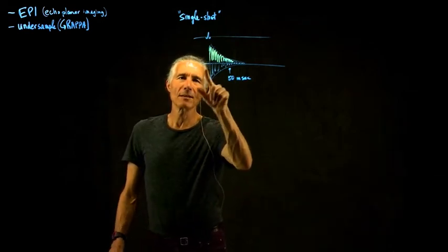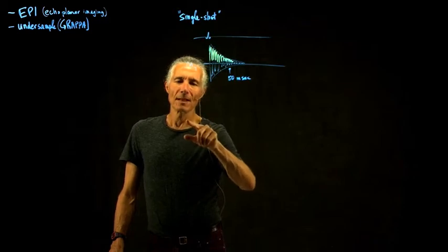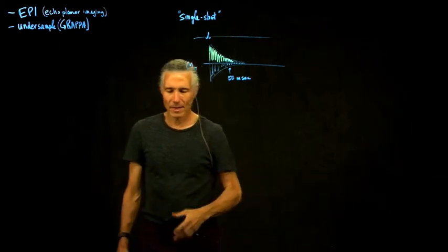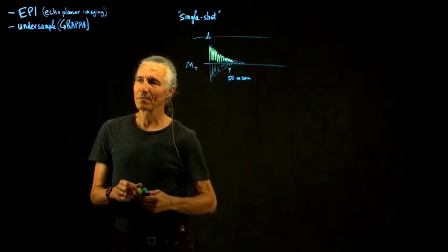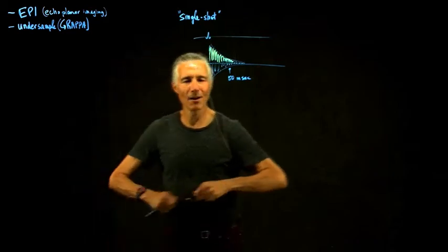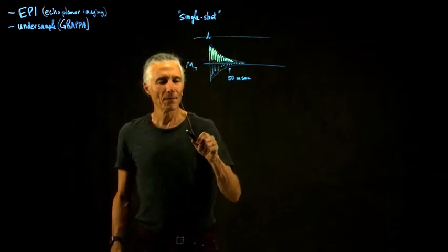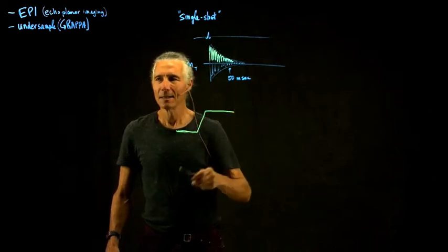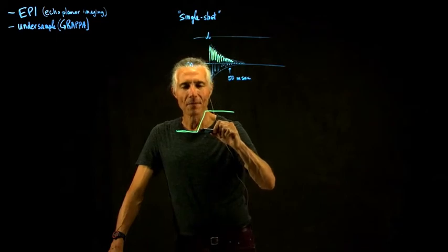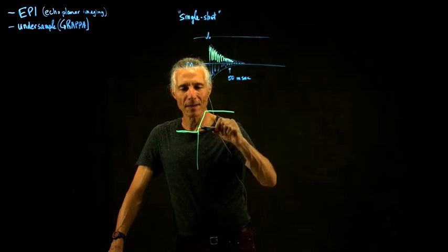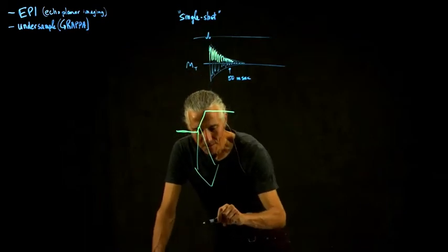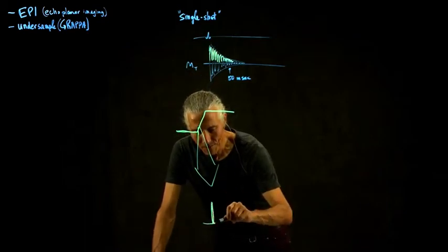And in the early days, they used amplifiers that were kind of like a stereo amplifier, and that doesn't make as efficient use of the transistors. What's done now is, if you want a gradient waveform that looks like this, and you blow up what's going on in a little tiny piece of that gradient waveform, the amplifier is just switching on and switching off like this.